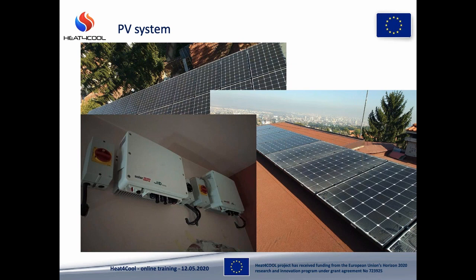The SolarEdge P500 optimizer system will facilitate much greater power generation compared to either a string inverter or a direct current power system, due to the heavily shaded nature of the roof and the limited range within which the heat pump can receive direct current power inputs.